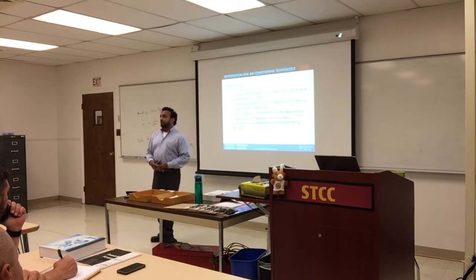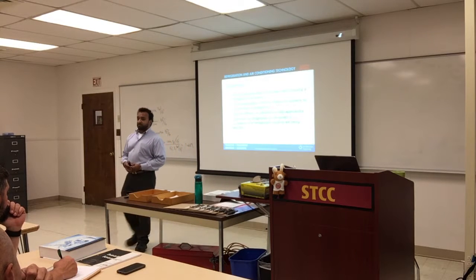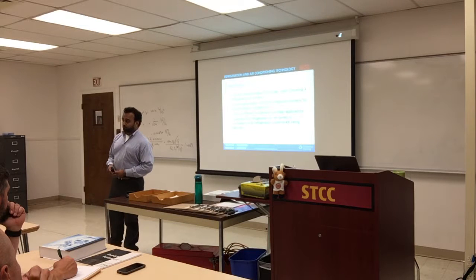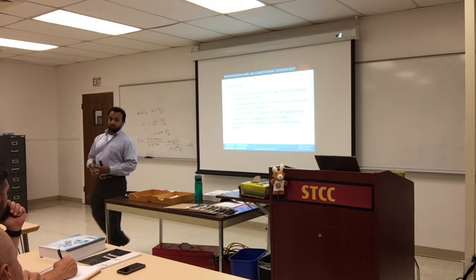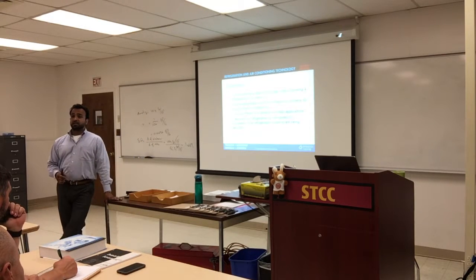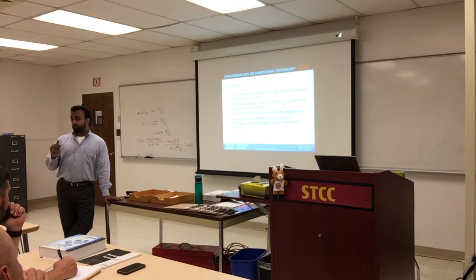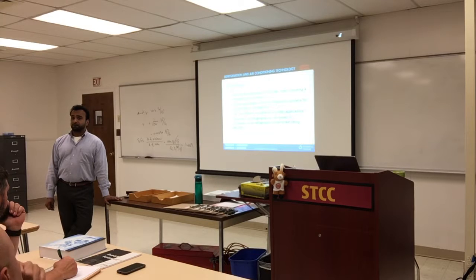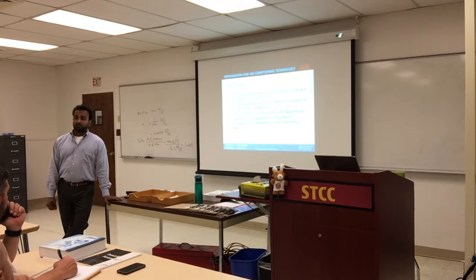And thereby, you're also not allowed to mix them in a container because those are to be recycled. You're supposed to put all refrigerants in their own containers. If it's a reclamation container, you should label it reclamation container and have it sent out. And they're all color coded to reduce the confusion.